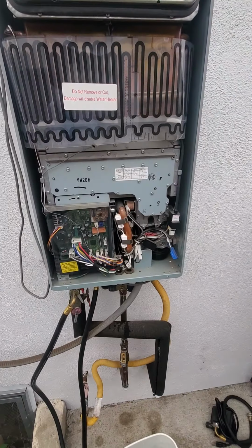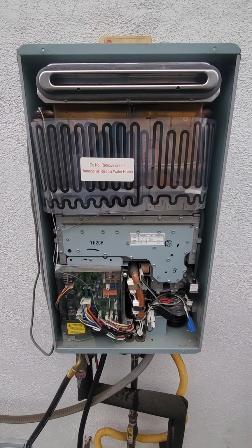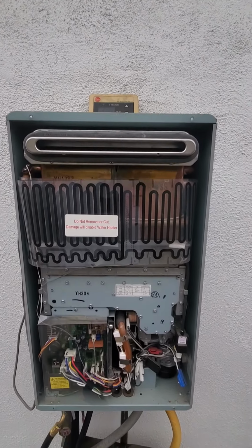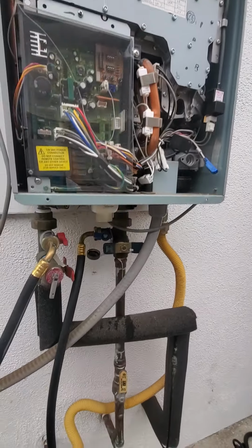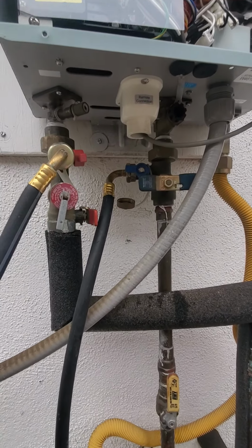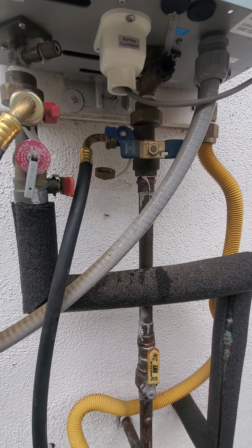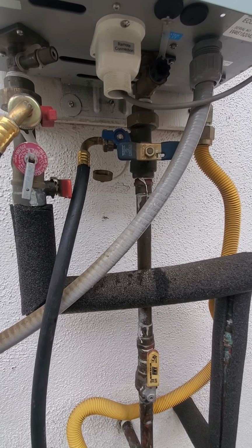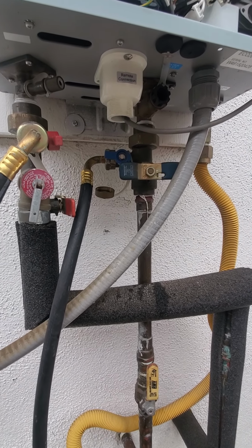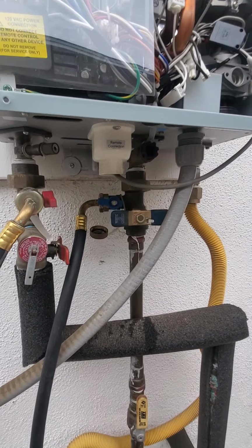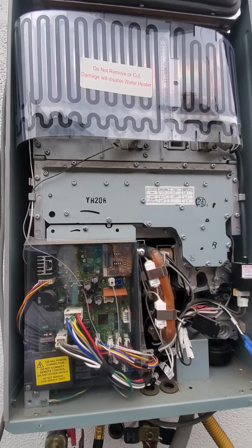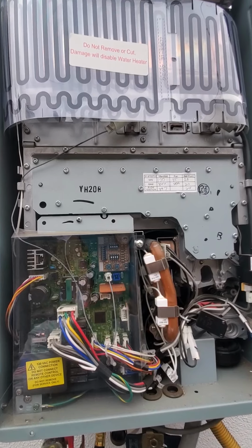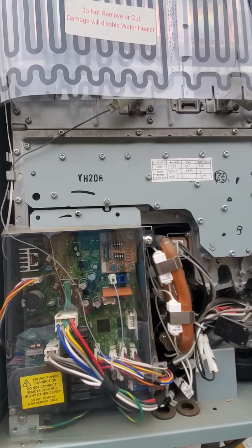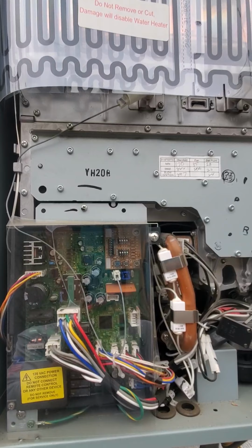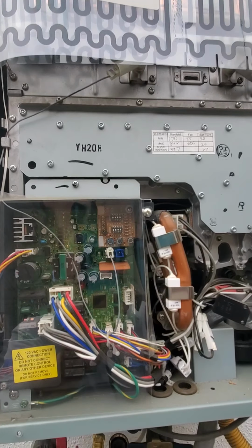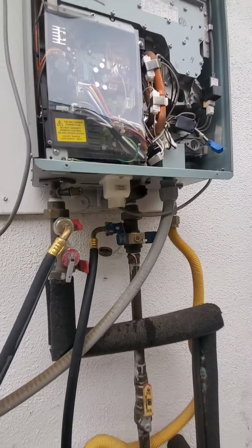So here's our tankless water heater. This is a Rheem model. This is actually pretty basic, very basic cleaning descale. What that descale does is remove all the deposits that are inside the heat exchanger. We don't see the heat exchanger in here, but it's definitely in there. And what we're doing now is cleaning off all those hard water mineral deposits that get stuck within that heat exchanger.